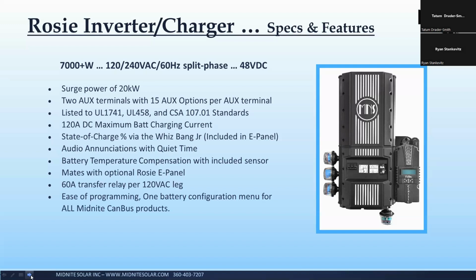The electrical specifications for the Rosie, as I mentioned, it is 7 kilowatts, 120/240, 60 hertz on a 48 volt battery. It has a 60 amp transfer relay, so 60 amps per leg, 120 volt leg. That said, you can actually take the Rosie, go in programming and tell it you want it to be an export 230, 50 hertz, and it will do that for you. There's a bunch of warnings and caveats, that you make sure you're not connected to your system while it's running and all of that. But you can also configure the Rosie as a 120 volt only inverter if you, for some reason, needed 7 kilowatts at 120.